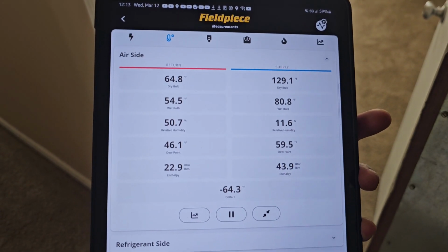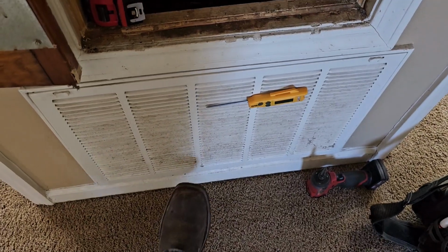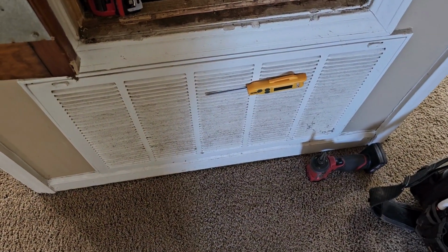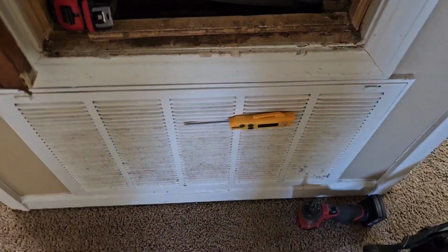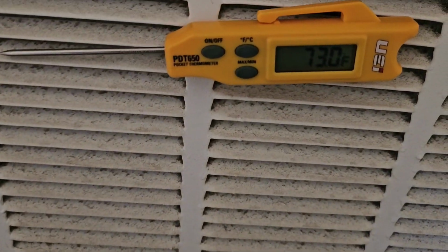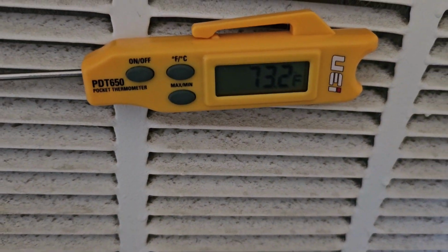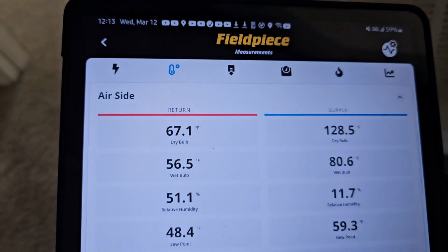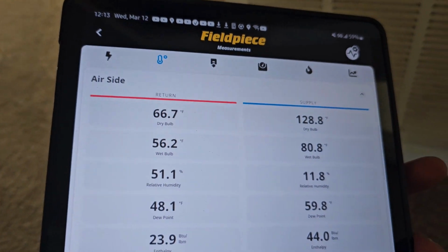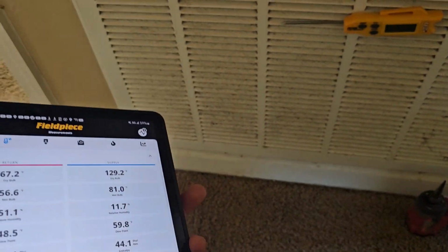So as you can see, this is what the Delta T is looking like. I have my Fieldpiece probe behind the filter, inside the actual return area, just to see if there's much of a difference. It says it's pulling in 73 right here, but the bulb inside is reading 67 in that actual space.